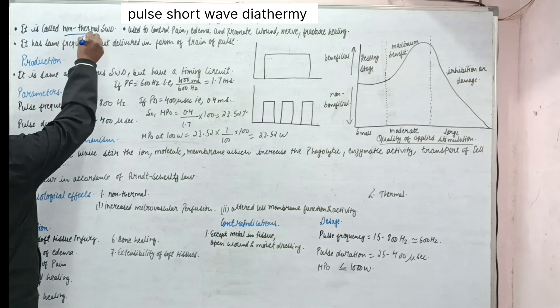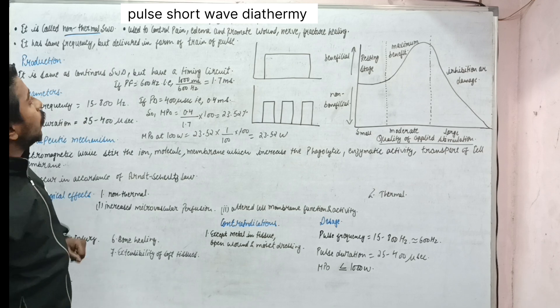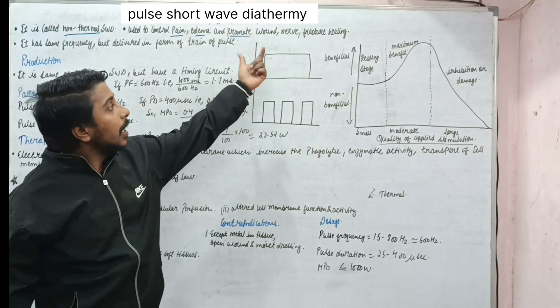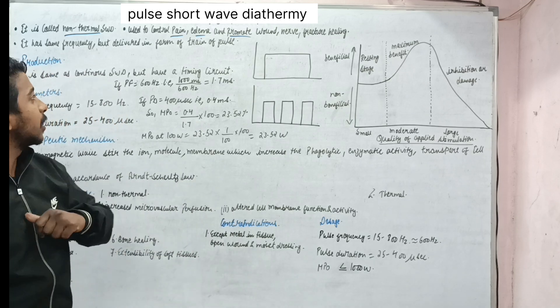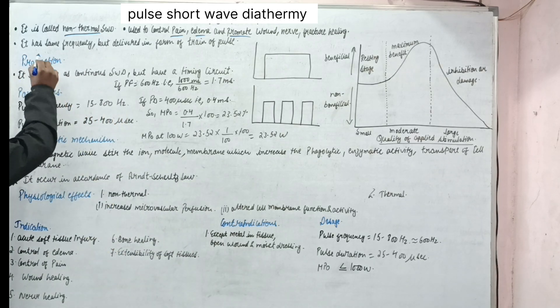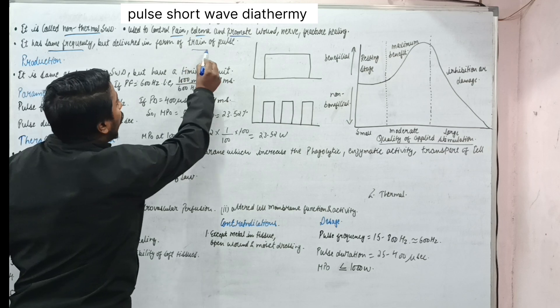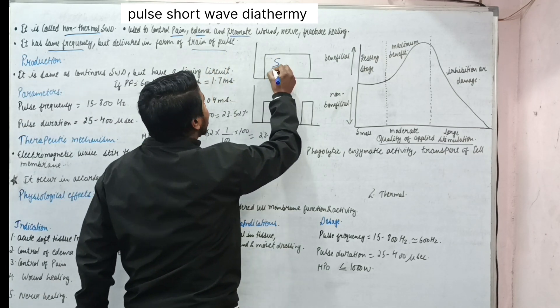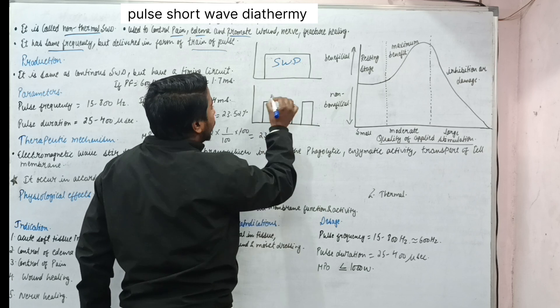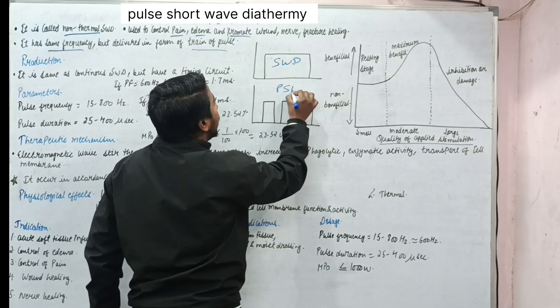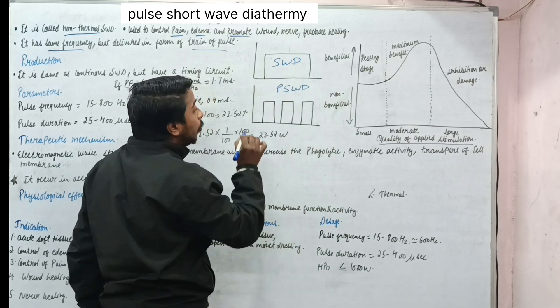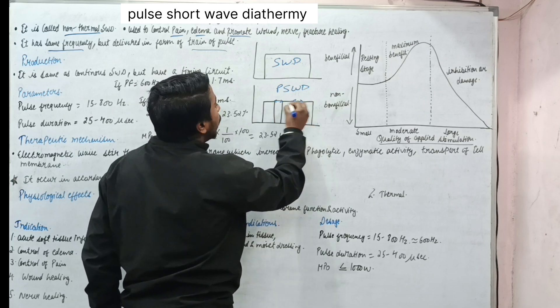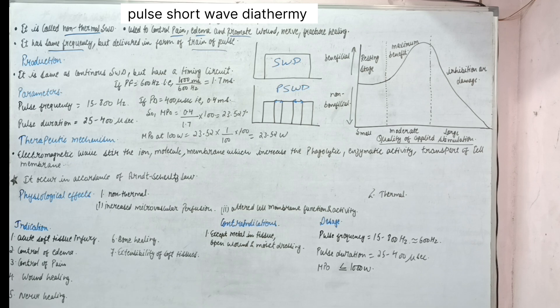It is also called non-thermal SWD. It is used to control pain, edema, and promote wound, nerve and fracture healing. It has same frequency but delivered in the form of train of pulse. So this was the continuous SWD, but this one is pulsed SWD. Why? Because it does not have continuous production. It is having this rest period, this rest period.